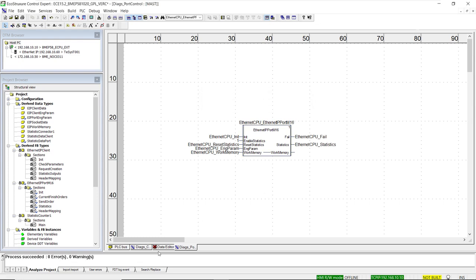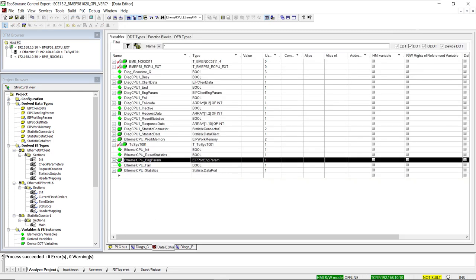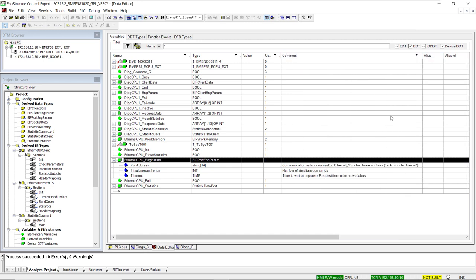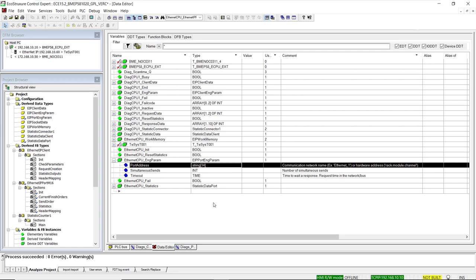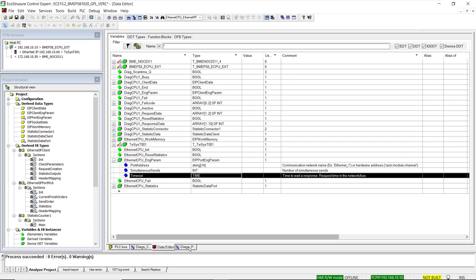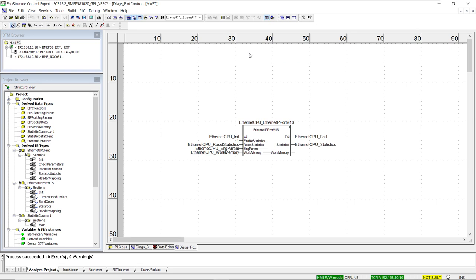There are important communication parameters to set in the engineering parameter structure connected to the fourth input pin of the port function block. Inspecting this structure in the data editor reveals three fields: the port address — in this case 0.0.3 for the CPU, or 0.slotNumber.0 for a NOC module — the number of simultaneous messages that can be sent, and the timeout parameter. Move function blocks are used to transfer values into the first two fields.